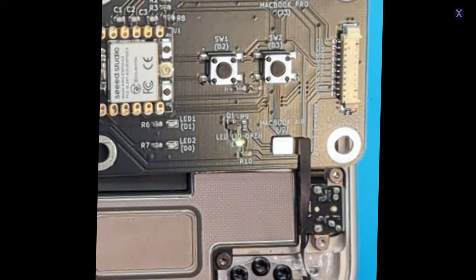So now what we need to do is tell this to calibrate. A way you can do that is we need to find the 0 point of our open and close, right? Since it thinks it's open right now, we need to tell it to look to see if it's closed right now. So we're going to click this button, and this button is going to show on the LED 1 that it is blinking, and that means it's starting to find that 0 point. When it gets to a solid color, that usually means that it's been calibrated.